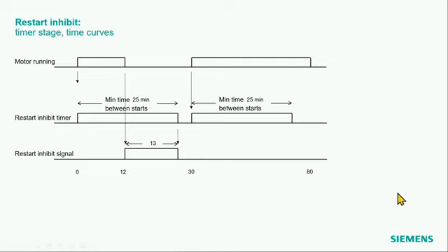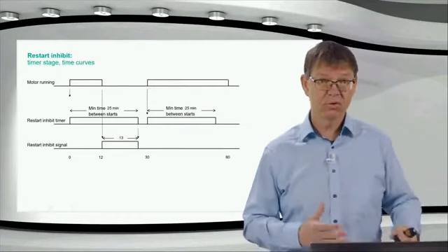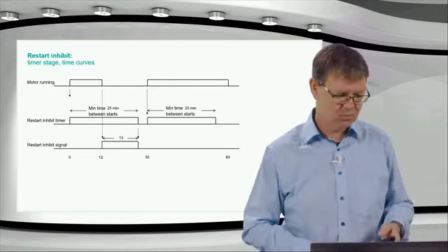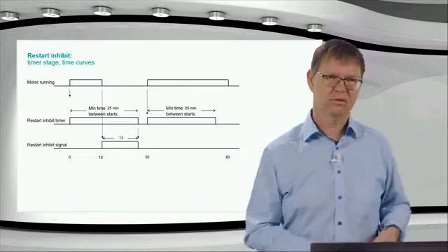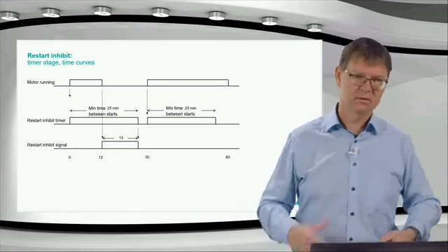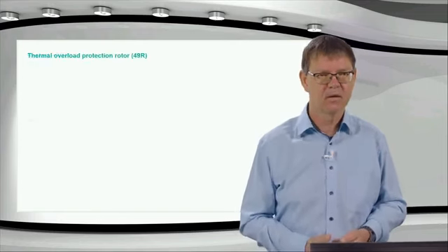And that's basically this part of the function. So we have a subdivision. We have 3 functions there. The thermal one, which is maybe the more complex one, and then 2 simple functions like a counter and a timer additionally. If you get data like that, then you can use those 2 additional functions or stages. They are implemented as stages in the relay.